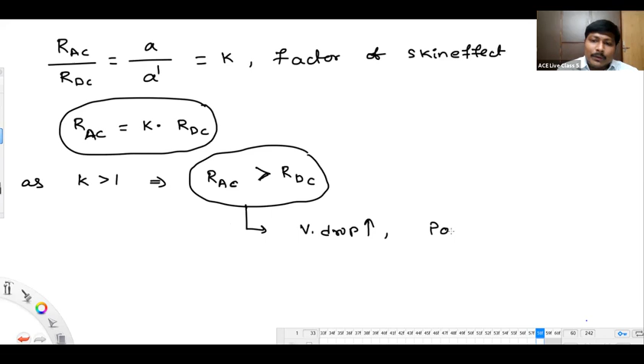So what's the problem of having more resistance for the conductor? Definitely power loss is more, voltage drop is also more. Those are definitely disadvantages of having higher resistance for the conductor. So you can write now: because of this, voltage drop will increase as well as power loss also increases. These are the disadvantages.